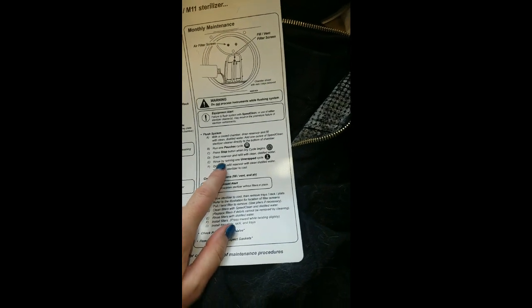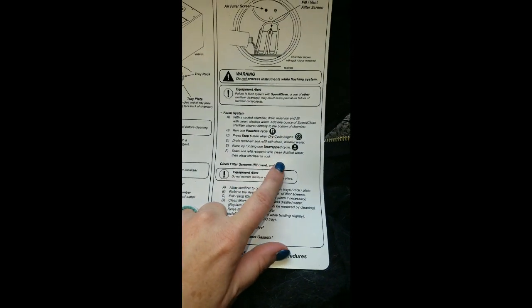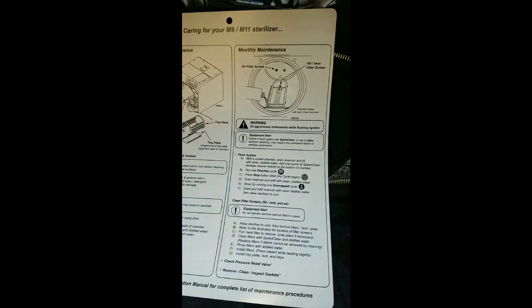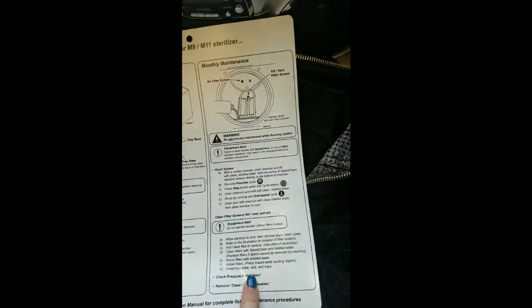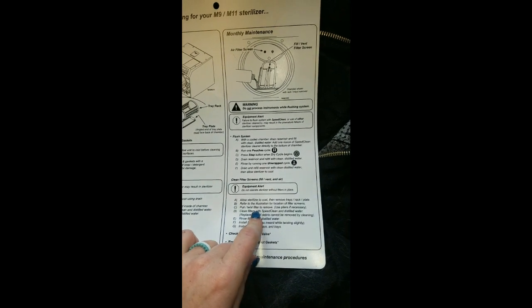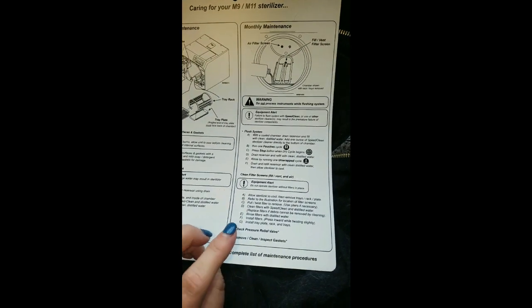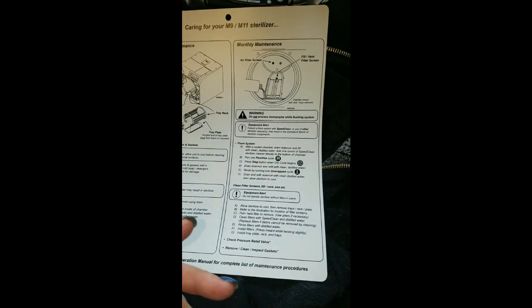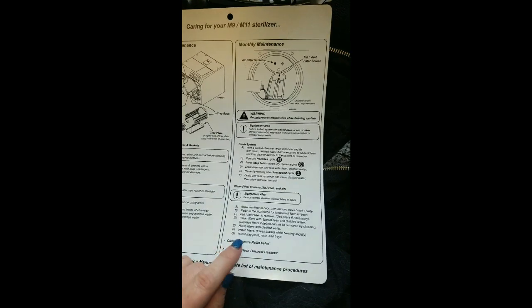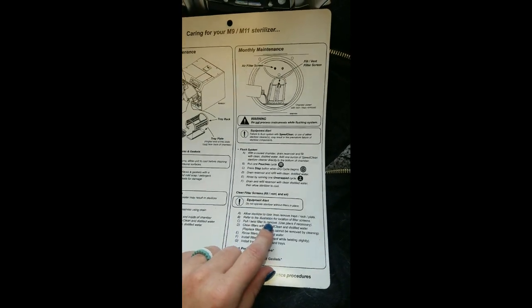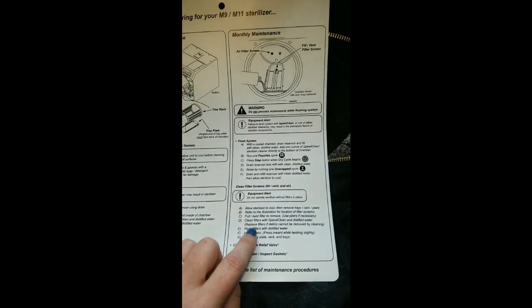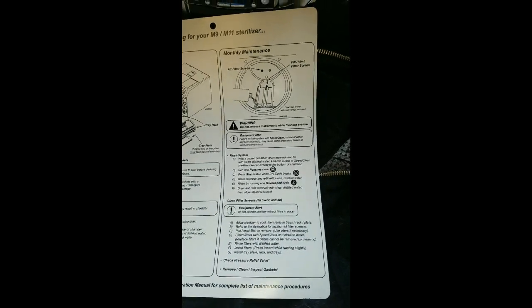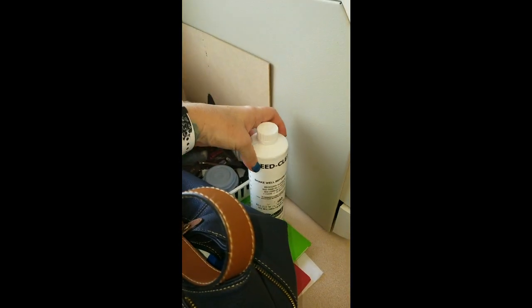And we have several gallons of distilled water on hand at all times. Then we're going to rinse by running the unwrapped cycle, which is this one. And then at that point, we'll drain and refill the reservoir with clean distilled water. So usually we use 2 to 3 jugs in the monthly maintenance cleaning process. You're also going to want to clean the filter screens, and you'll wait for the sterilizer to cool, remove the trays and everything, clean all that. If you need pliers, which sometimes we don't, to remove the filter, that's also okay. You'll clean the filters with the speed clean, which of course again is this right here.